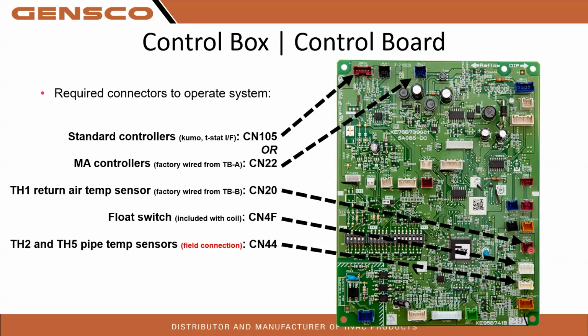CN20, this one is also a factory connector right here. Don't need to do anything with this, but your return air thermistor that goes into the return of this thing will need to be hooked up to that. Except where you're going to hook it up is going to be on the actual terminal block B. And again, we'll get into that a bit.